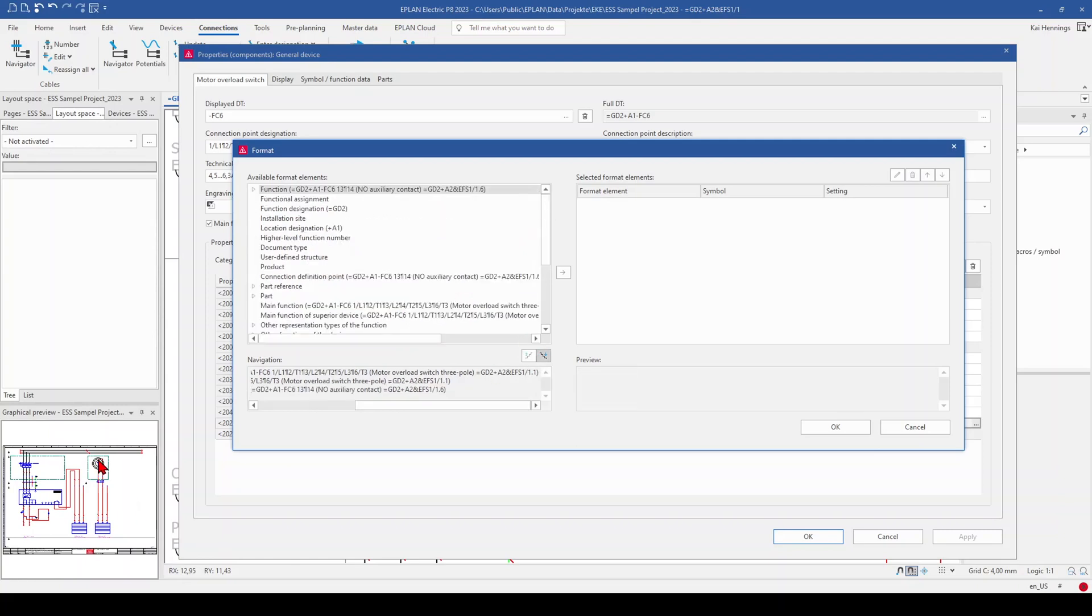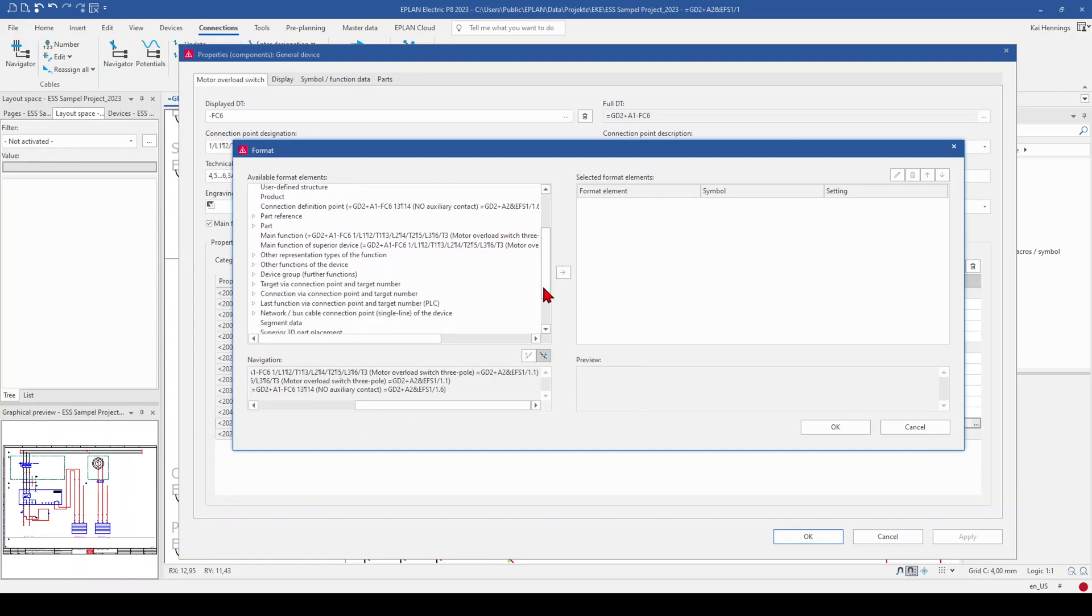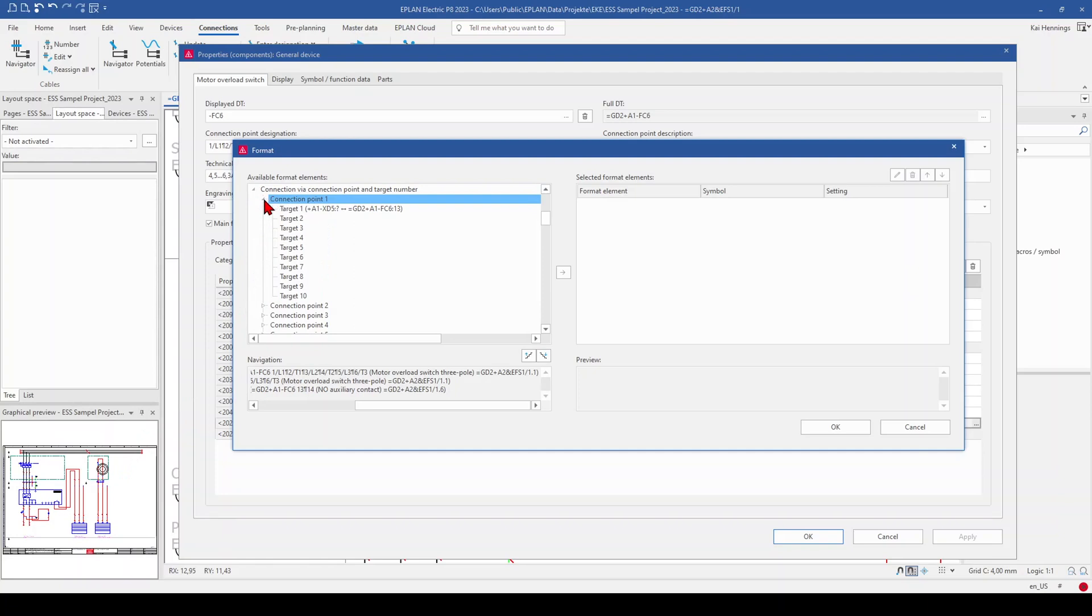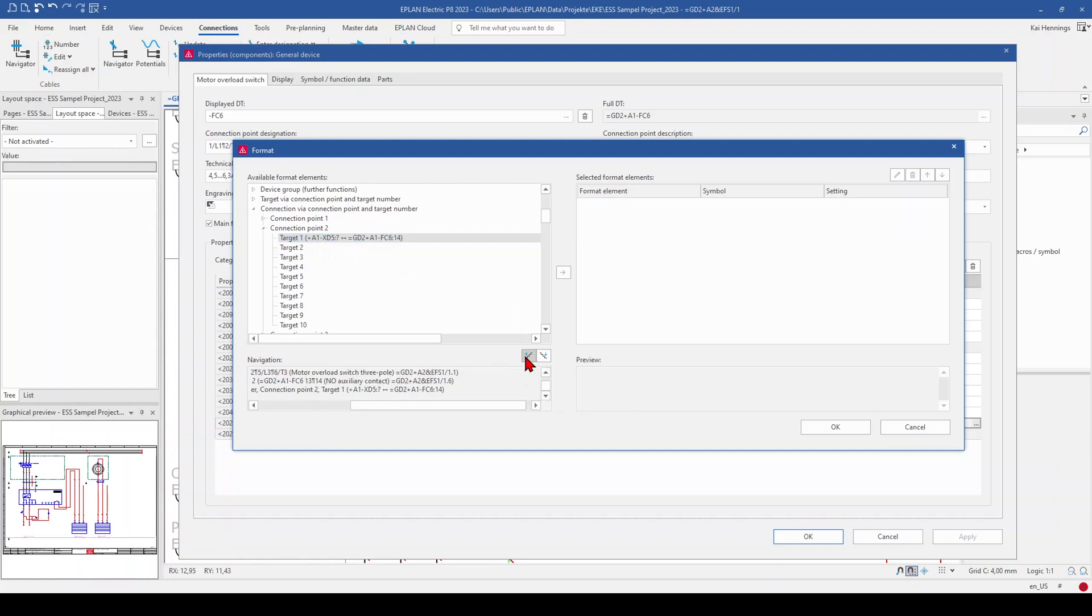And now we need to jump down to the digital input connection of the PLC box. So therefore we go to connection via connection point and target number. And here you can see when you click on connection point 1, it's this side. And when you click on connection point 2, it's the other side. So because the digital input is on the left side here on the PLC box, we use this connection point and go to the next level.